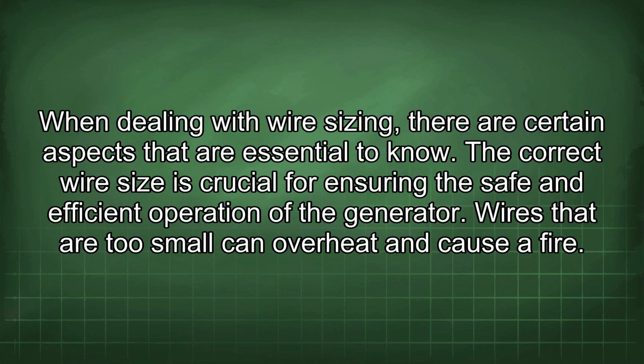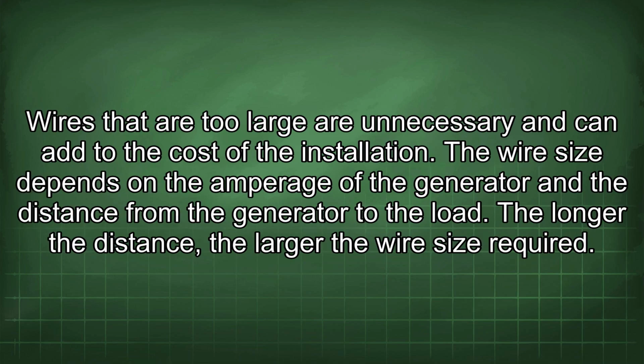When dealing with wire sizing, there are certain aspects that are essential to know. The correct wire size is crucial for ensuring the safe and efficient operation of the generator. Wires that are too small can overheat and cause a fire. Wires that are too large are unnecessary and can add to the cost of the installation. The wire size depends on the amperage of the generator and the distance from the generator to the load. The longer the distance, the larger the wire size required.